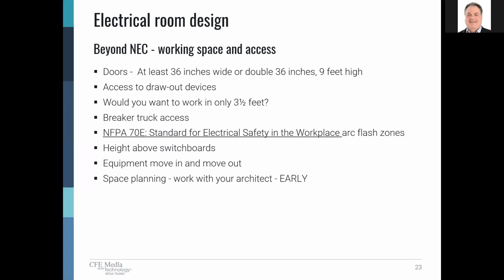On switchgear, you need breaker truck access. We have to consider, of course, arc flash and arc flash zones. The amount of PPE gear is dependent on the amount of arc flash energy, incident energy, and the distance you are away from the gear. This can affect non-technical people who are supervising work. More room, just safer and better. We talked a little bit about structural ceilings and equipment space. Really, the height above switchboards and switchgear in the main electrical room should be considered.